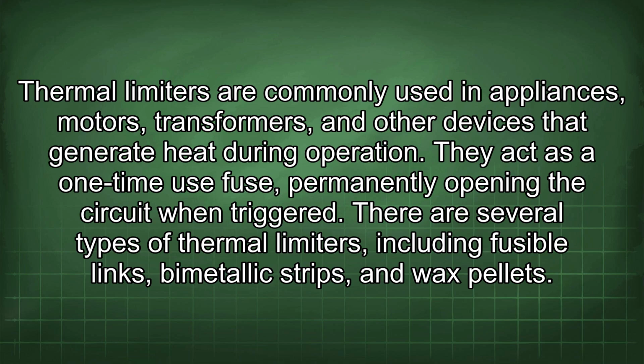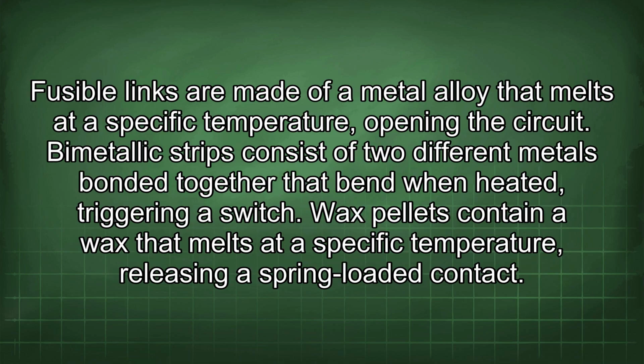There are several types of thermal limiters, including fusible links, bimetallic strips, and wax pellets. Fusible links are made of a metal alloy that melts at a specific temperature, opening the circuit. Bimetallic strips consist of two different metals bonded together that bend when heated, triggering a switch. Wax pellets contain a wax that melts at a specific temperature, releasing a spring-loaded contact.